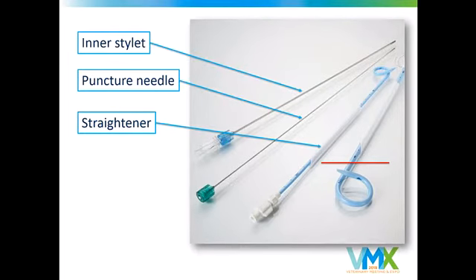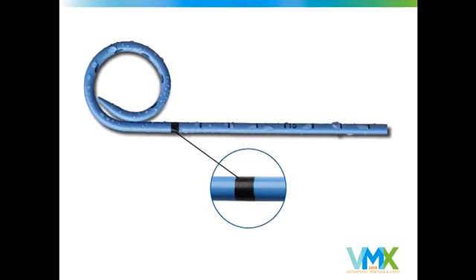One of the things you need to appreciate on a pigtail catheter, so I put this red line here, is that when you've placed it in whatever your body cavity is, you have to make sure that you've got all of the loop inside the body cavity. This one just has one perforation, but many locking loop catheters have several perforations, and they'll sit all the way around on the loop. Generally, if you're just above the loop, you've got all of the perforations in the body cavity. So always get a sense of how much catheter has to be in so that I'm sure all of my perforations are definitely inside the body cavity.